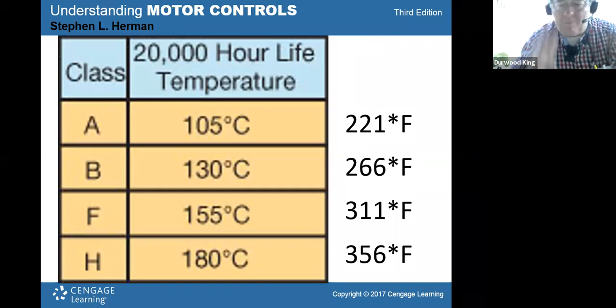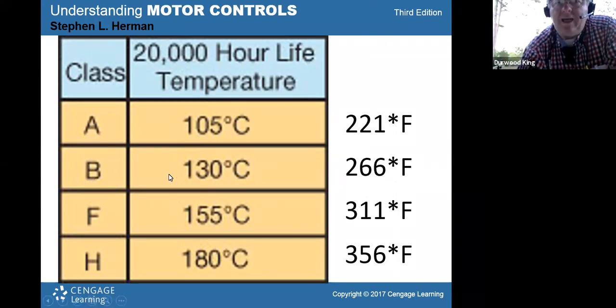So this is a real biggie right here if you're around ovens. And if it has a B rating, it can handle up to 266 Fahrenheit. An F can handle 311 Fahrenheit, so you're talking oven duty motors there. And an H could handle as high as 356 Fahrenheit. So this is information that's very important if you're dealing with ovens.